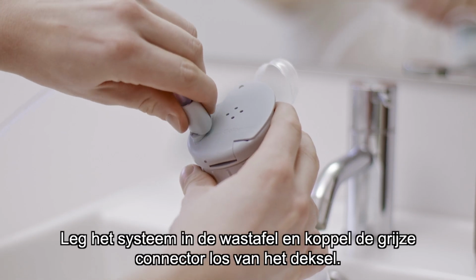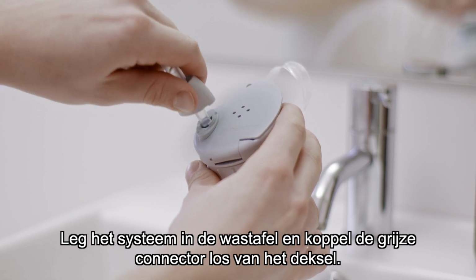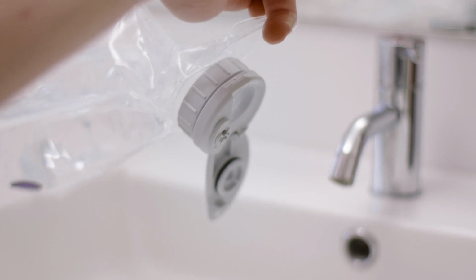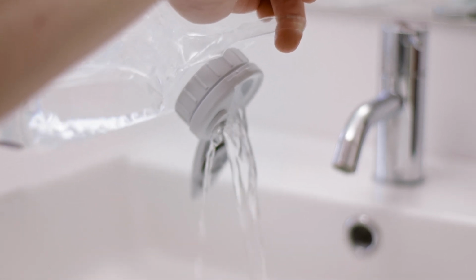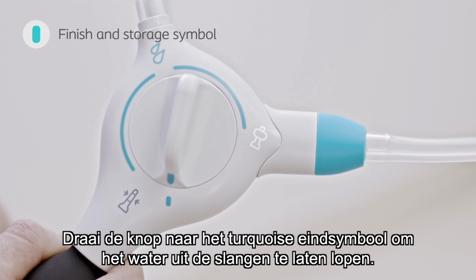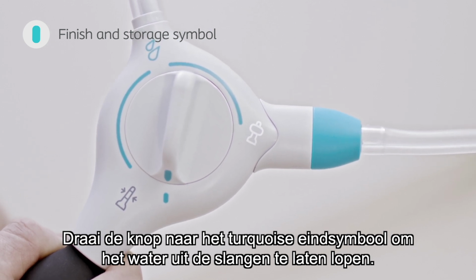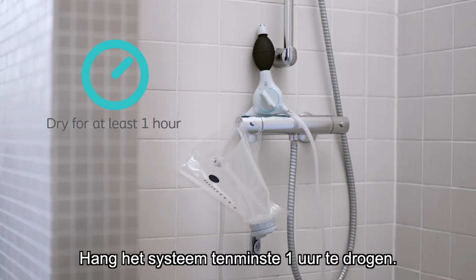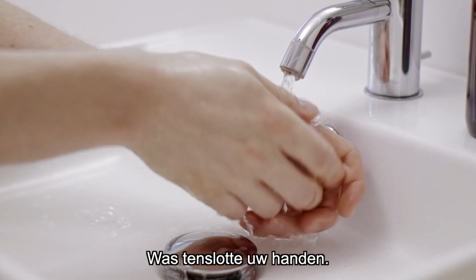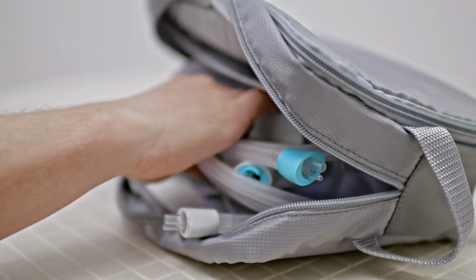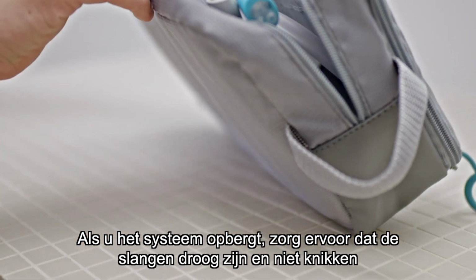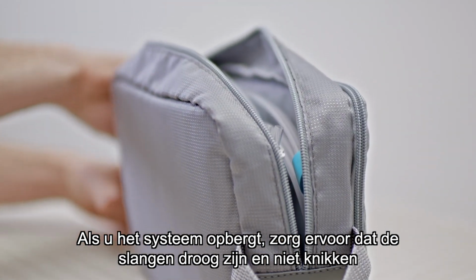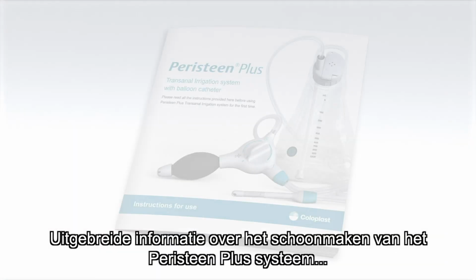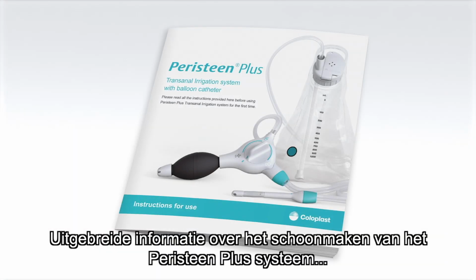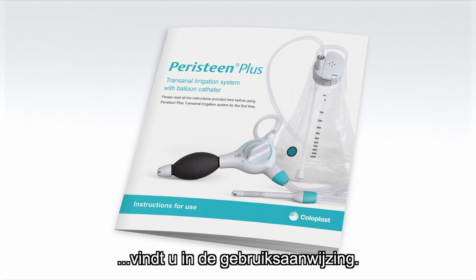With your system in the sink, twist the grey connector anti-clockwise to disconnect it from the lid and empty the water bag. Then turn the knob to the finish and storage symbol. This will release the water from the tubes. Now hang the system to dry for at least an hour. Finish by washing your hands. When you store the system, make sure that the tubes are dry and without kinks. For detailed information on how to clean your Peristeen Plus system, please consult the Instructions for Use document.